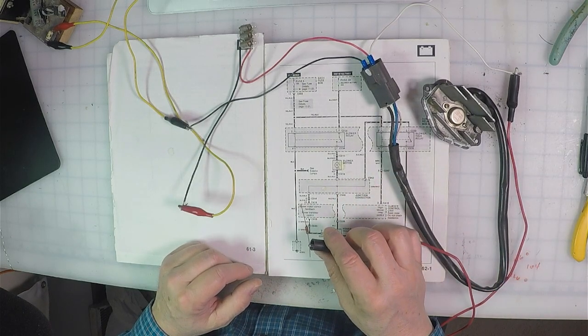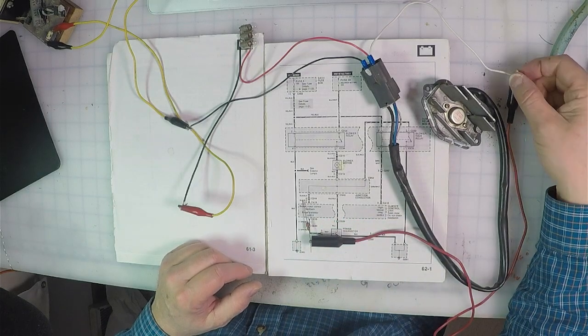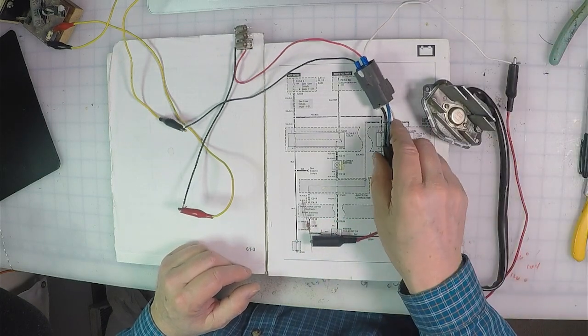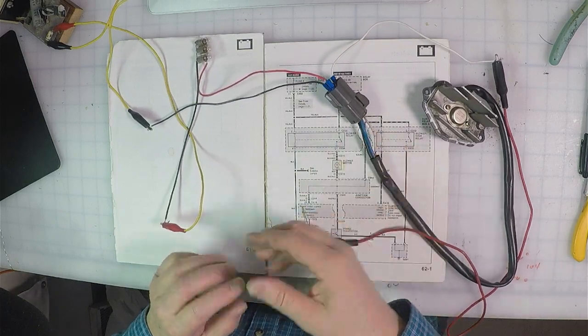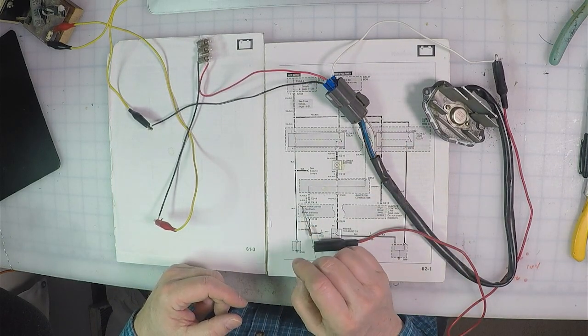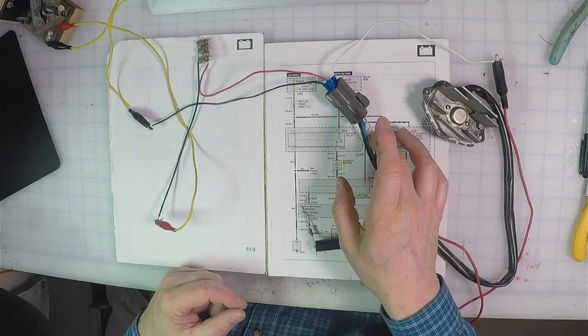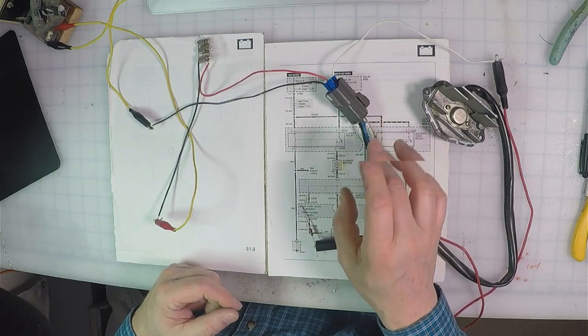test it like this, or just monitor the voltage at the white wire as you go through the cycle through the speeds of the climate control, go up and down in speed, and you'll see the voltage level on the white wire go up and down.